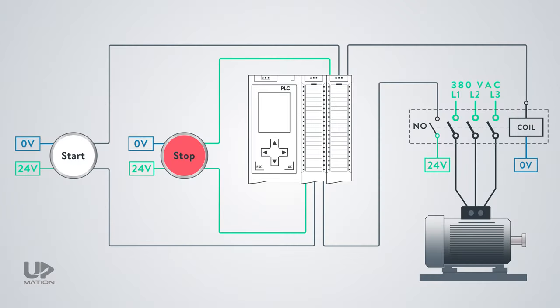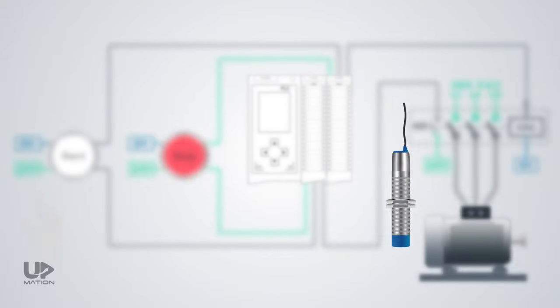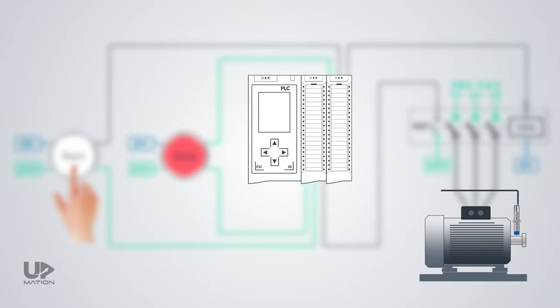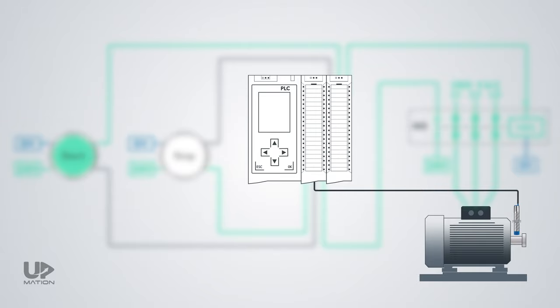In addition to the contactor functionality check, sometimes, where is possible, we should use a proximity sensor on the shaft of the motor to make sure if the motor is really running and is not stuck by any means. In this way, as long as the proximity sensor's input to the PLC card is getting on and off with a certain frequency, we are sure that the motor is working.